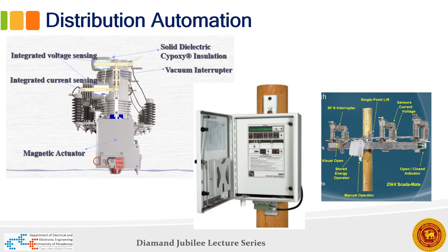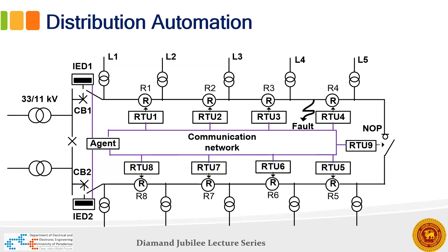There are also lots of new devices coming for distribution automation. These are S&C devices being deployed in Scotland. The basic idea is you have pole-mounted sectionalizers with current and voltage measurements that can operate automatically, controlled through a pole-mounted control box. Using that, you can do agent-based control of your network. If there's a fault on one part of the network, the devices can talk to each other to ensure most of your network stays live, disconnecting only the small faulty part.